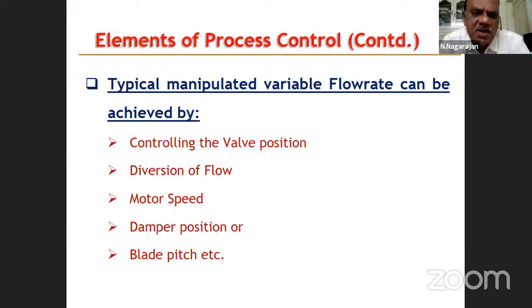A typical manipulated variable, flow rate, how do you control the manipulated variable? Okay, for example, flow rate, by controlling the valve position. So you have a flow control valve, you can vary the opening of the valve, either increase the opening or reduce the opening to achieve the required flow rate. Diversion of flow, sometimes we may have a branch line where you can divert some portion of the flow. This comes in bypass control.